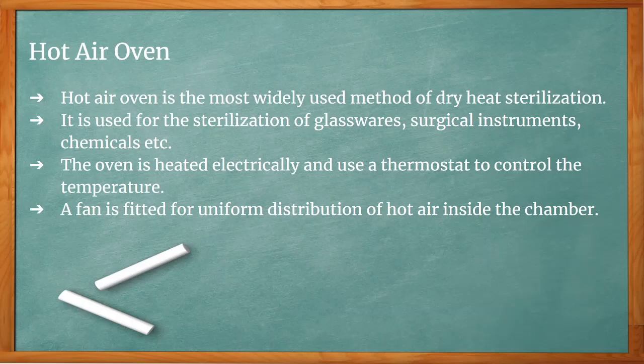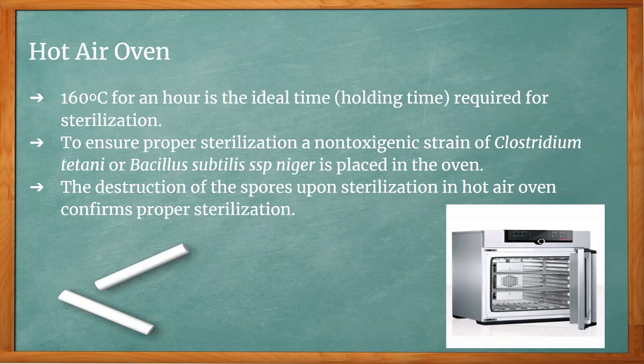Hot air oven is the most widely used method of dry heat sterilization. It is used for the sterilization of glassware, surgical instruments, chemicals, etc. The oven is heated electrically and uses a thermostat to control the temperature. A fan is fitted for uniform distribution of hot air inside the chamber. The ideal sterilization condition is 160 degrees Celsius for one hour.